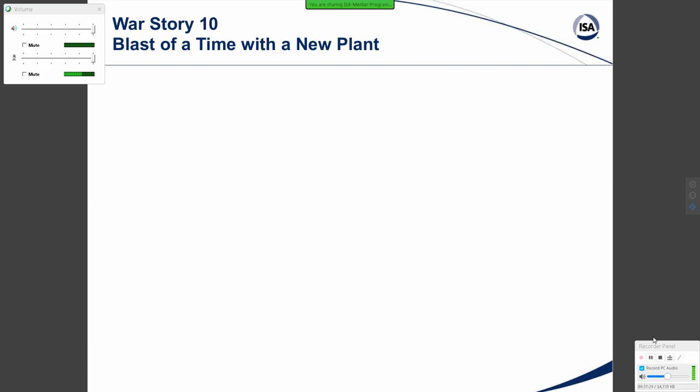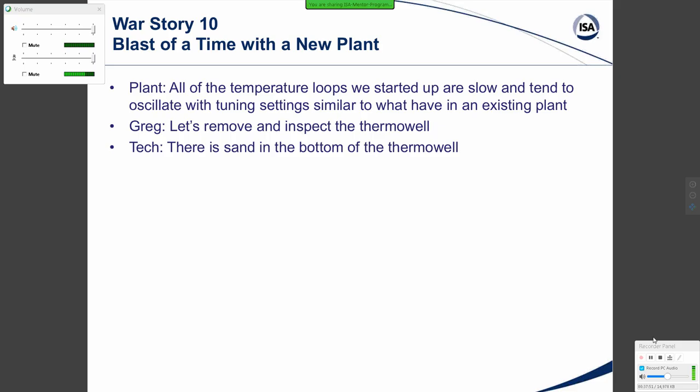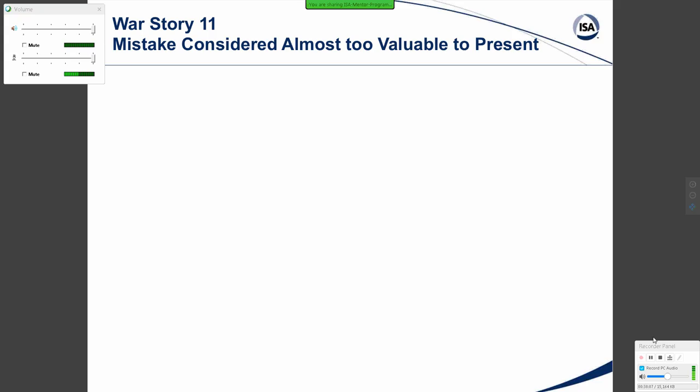War Story Ten: New plant startup. All of the temperature loops started up slow and tended to oscillate, with tuning settings similar to those in an existing plant producing the same product. I said, let's remove and inspect the thermowells. The technician found sand in the bottom of the thermowell — the sensors were not installed when the thermowell was in the pipe during sandblasting, resulting in an insulating layer of sand. We needed to disassemble and clean out every one. After they did that, the temperature loops were fine.